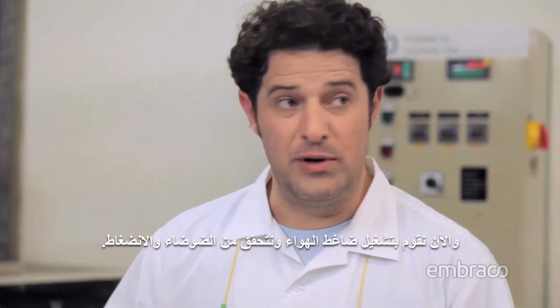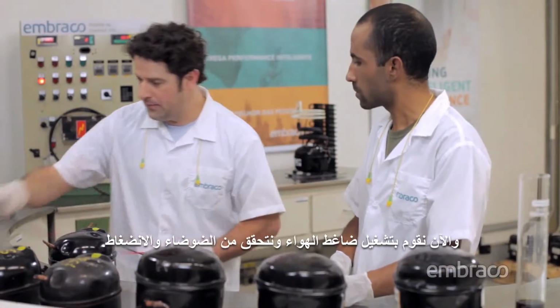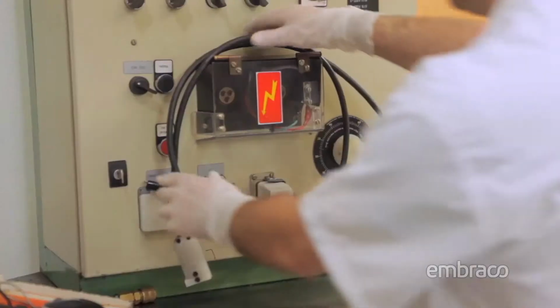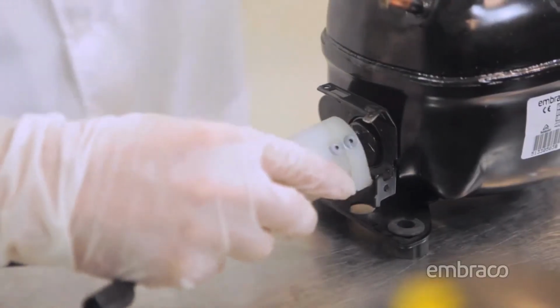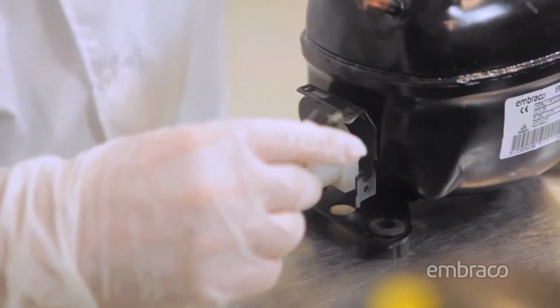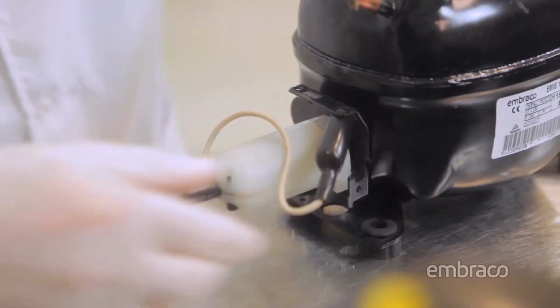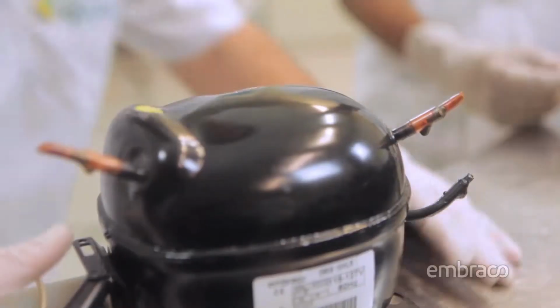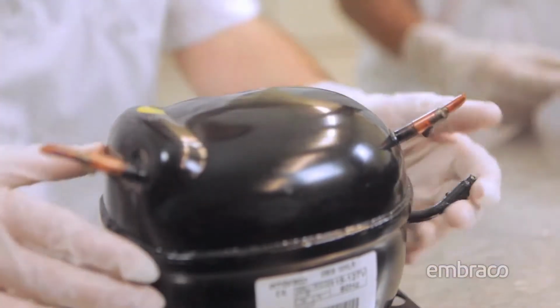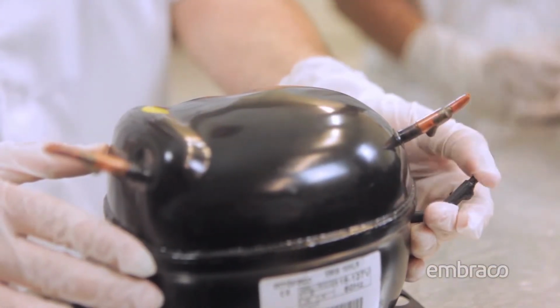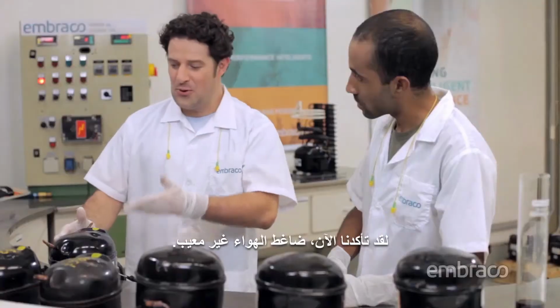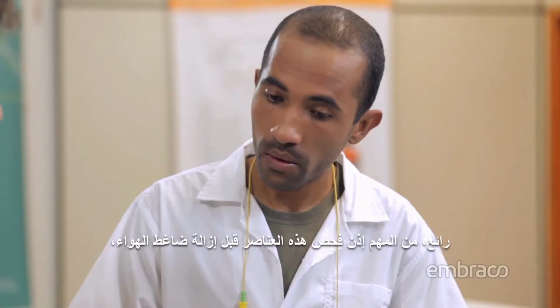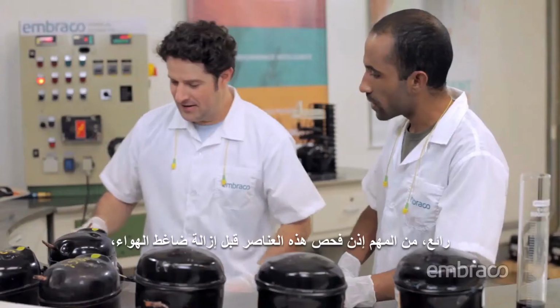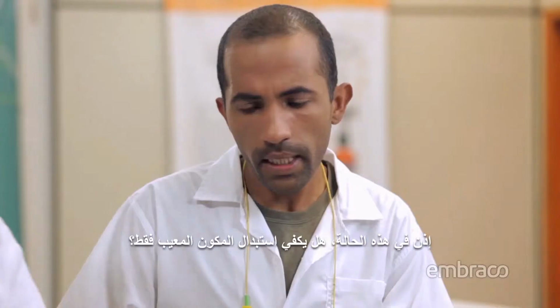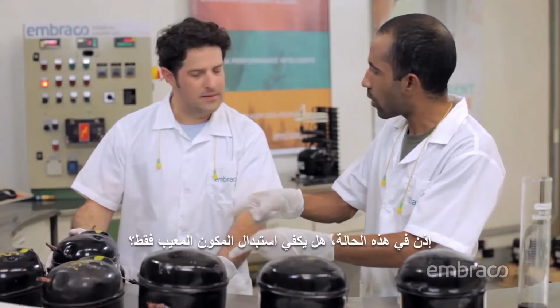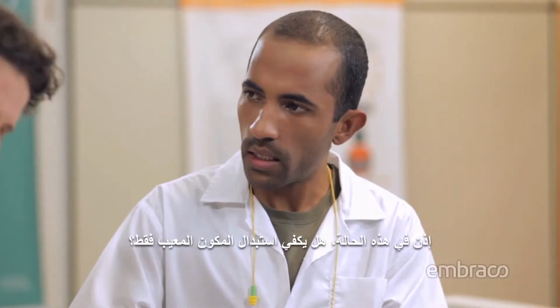Now let's turn on the compressor and check for noise and compression. Confirmed, the compressor isn't defective. Wow, it's really important to check these items before removing the compressor. So, in this case, would it be enough to just replace the faulty component?